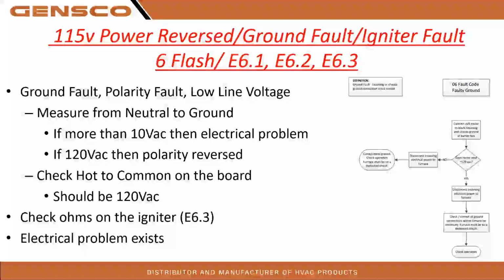So we have had situations where older homes get newer furnaces. It worked fine on the old diesel burner system that they had, but they have, like say, an Edison circuit within the home. And when we check across what we would consider black and white, we have 120 volts. But as soon as we go L1 to ground, L2 to ground, we have a mix of voltage, like 60 and 60 or 80 and 20. So those would be electrical problems, incoming power to the home, right? That would be like an Edison circuit or something like that, causing you some issues with your newer furnace. And then that could also cause flame rectification problems. Bad ground, stuff like that can cause that as well. So these codes you're really going to dig into power-wise, high voltage.